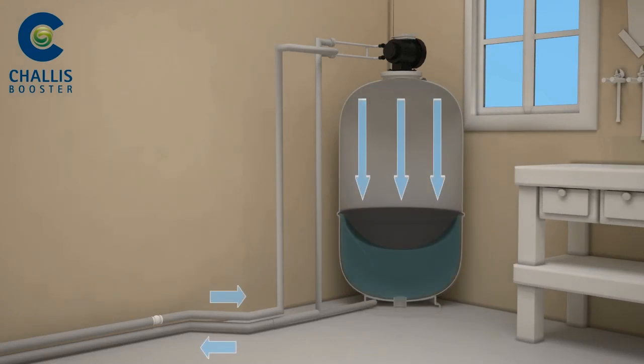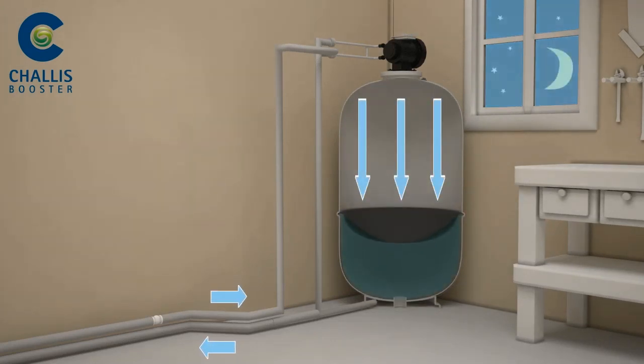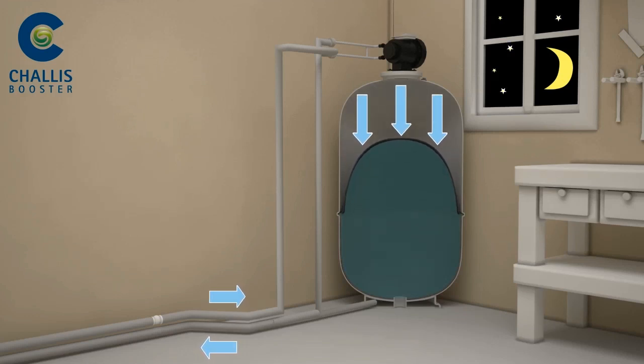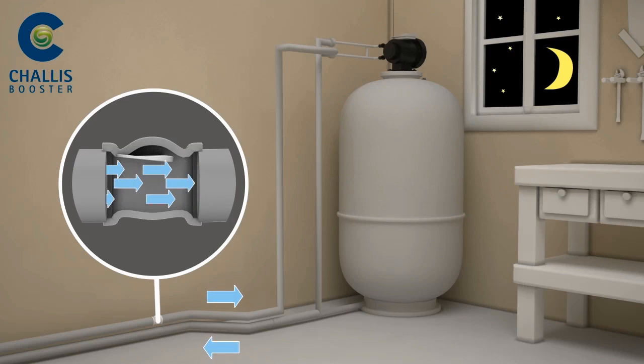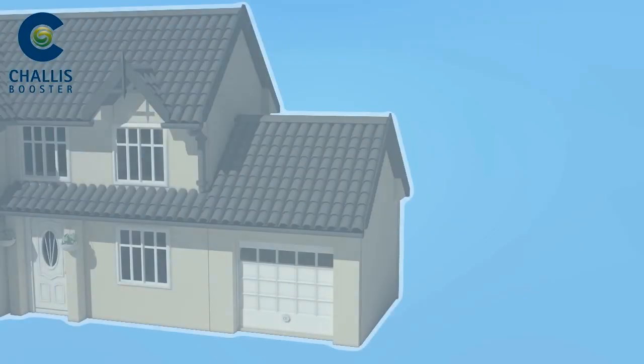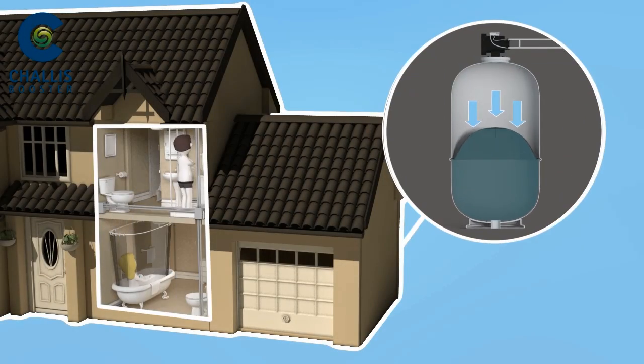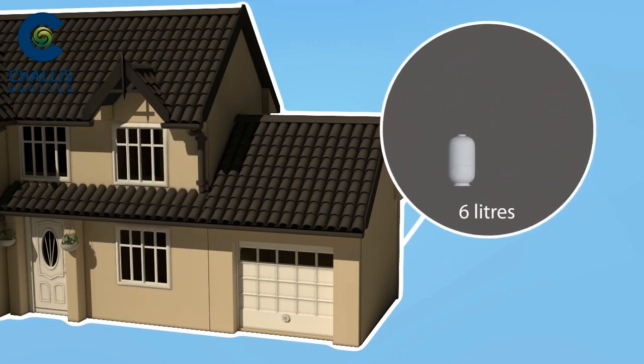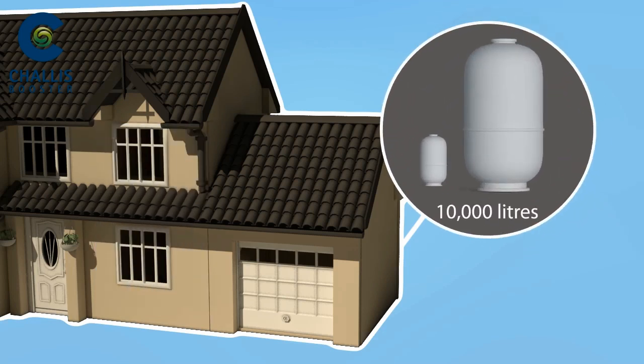Challis Booster works using a pressurized accumulator as a water reservoir. The reservoir is filled at times of low demand using pressure supplied by the water mains to pump up the cylinder. A non-return valve is used to lock the reservoir, creating a volume of pressurized water within the cylinder which can be drawn upon at times of high demand, such as in the morning. Water units range from 6 litres right up to 10,000 litres to suit the demand of your property.